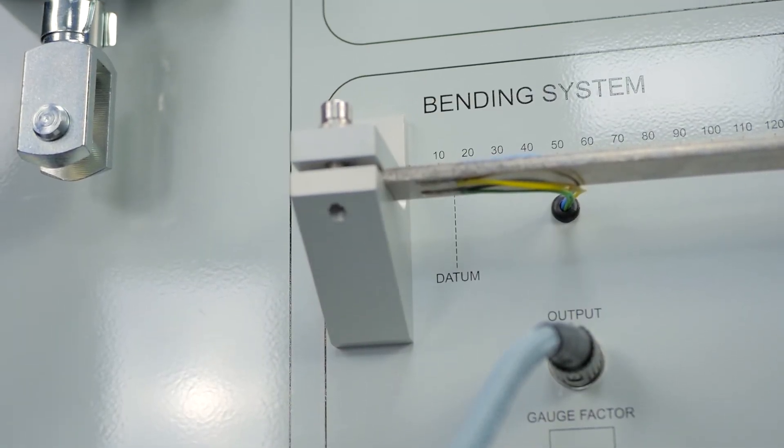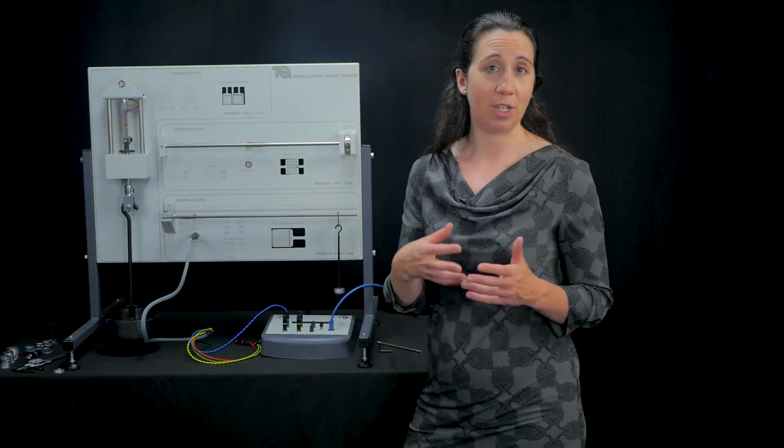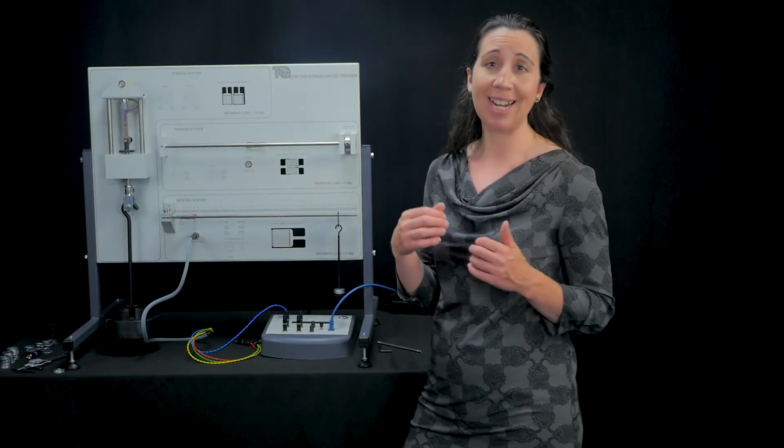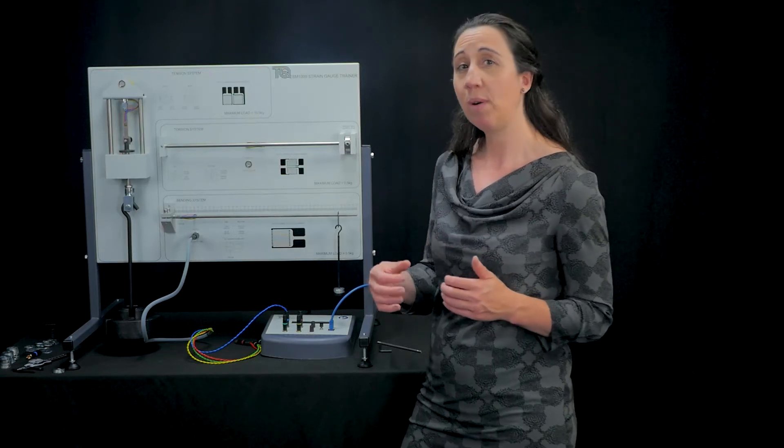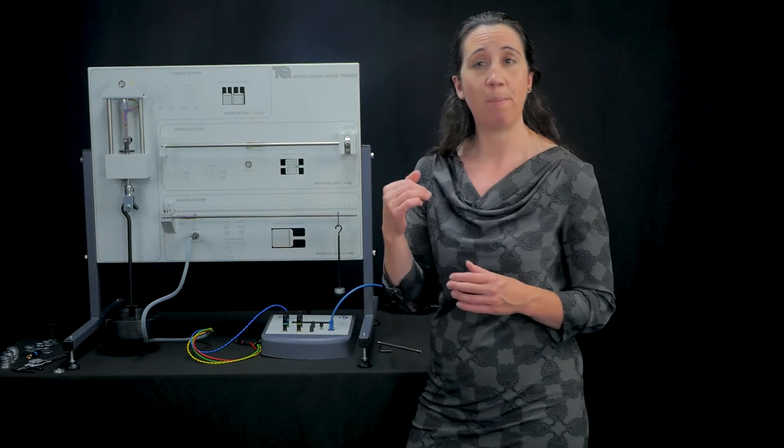There is a solid rectangular section cantilever beam held securely at this end. Four strain gauges measure the tensile and compressive strains directly in line with the beam. The two on top measure the tensile strain and the two underneath measure the compressive strain.